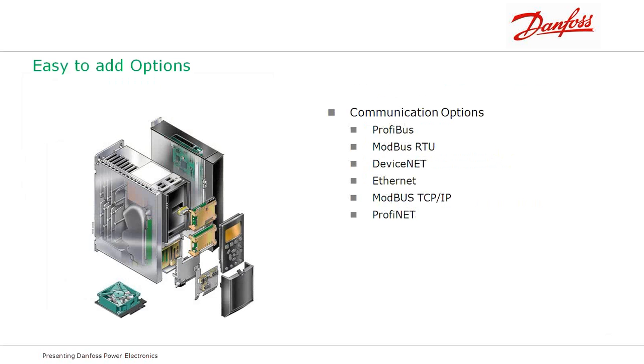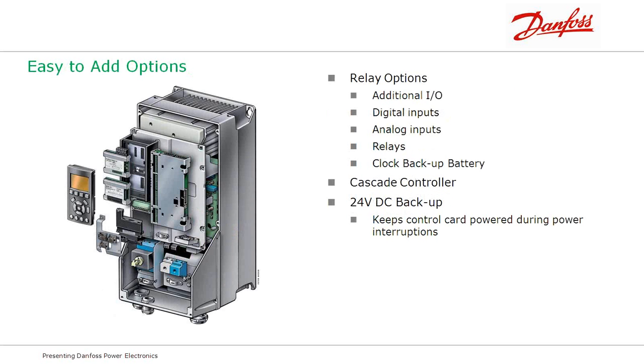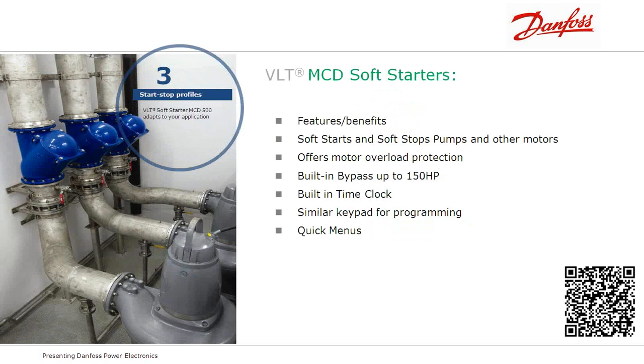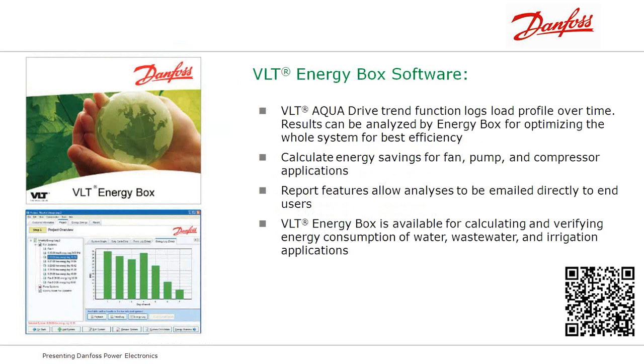Being able to add communication options and relays and additional inputs and outputs is a big, nice feature here. Plug-and-play technology. You literally open the keypad, plug the new unit in. You can see here on the right behind the keypad, the communication cards are always in the top, and the additional relay options are in the bottom. Danfoss also manufactures soft starters, which give you the ability to electronically ramp up and ramp down pumps in a softer way, reducing water hammer, making your equipment last a little bit longer.